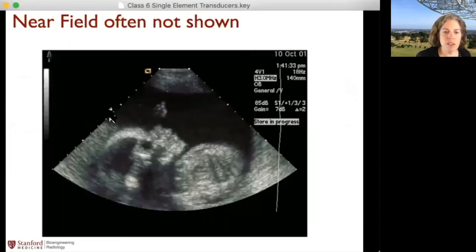When you're doing ultrasound imaging, the sonographer will set it up with a particular depth, and that's where it's going to set the elements to be most in focus. So on transmit, you can only specify one depth. On receive, you can actually change the focusing dynamically from all points as the echoes are coming back.